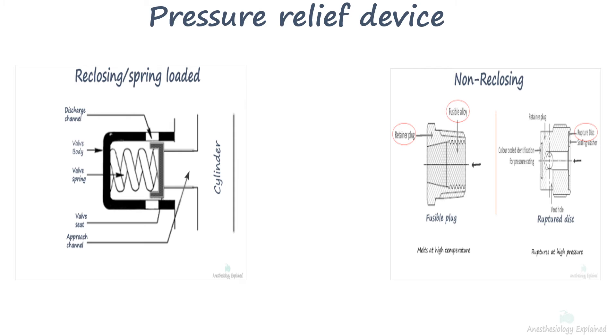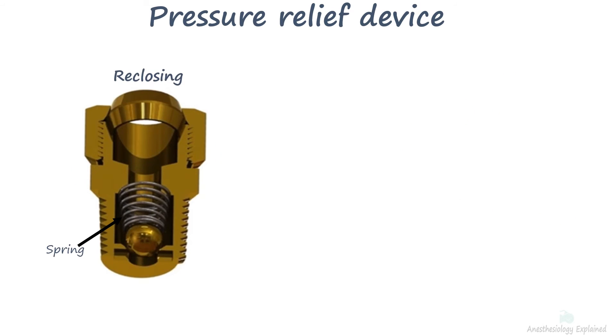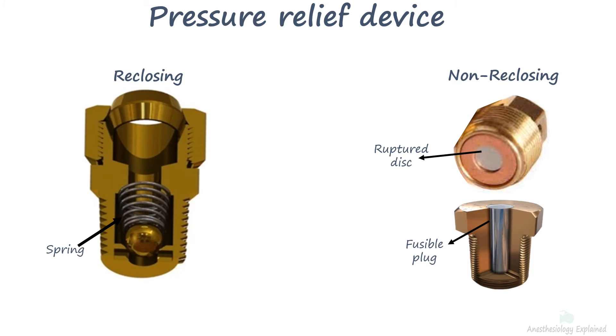Reclosing pressure relief devices are spring-loaded mechanisms designed to automatically reclose and prevent the discharge of contents once normal pressure levels have been restored. Conversely, non-reclosing devices do not reclose once the gas is discharged and pressure has normalized. These non-reclosing devices come in two primary variants: ruptured discs and fusible plugs. Some non-reclosing devices combine both ruptured discs and fusible alloys to enhance their safety.